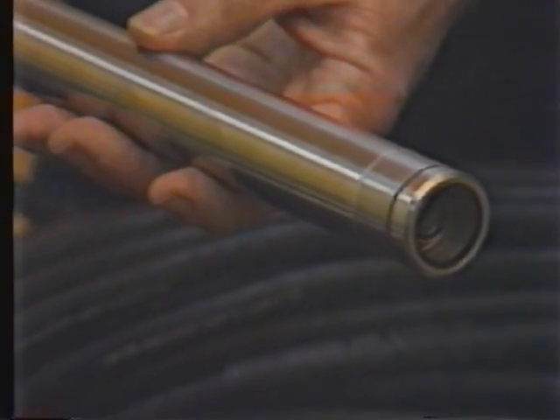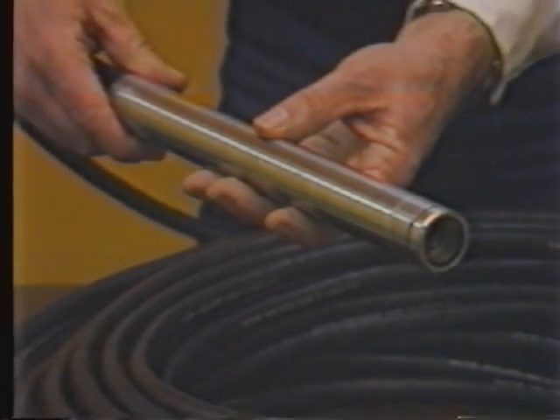The first visual evidence of damage was obtained when a miniature underwater television camera was lowered through an opening in the top or head of the reactor. The operation was called Quick Look and was the first of several television inspections supported by DOE that established there was a void where the top 5 feet of the fuel core had collapsed into a bed of rubble.